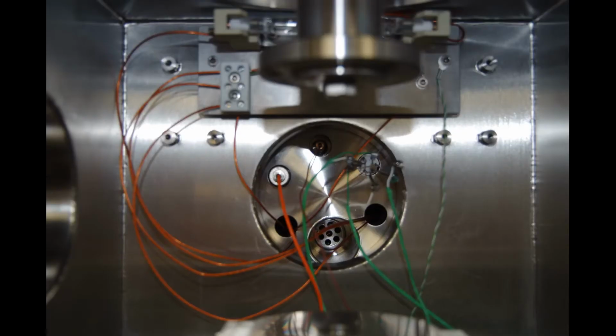On the back of the chamber there are electrical feed-throughs to provide the necessary connections. There are also halogen bakeout lamps. There are 3 thermocouple sockets at the back of the chamber. Socket 1 is for the lower specimen temperature. Socket 2 is spare. Socket 3 is for the washer thermocouple fitted to the back of the chamber for measuring bakeout temperature. A brown wire with a crimp ring is used to connect the lower specimen tooling to complete the electrical contact resistance circuit. A 3-way ceramic block is used for connecting the lower specimen heaters.